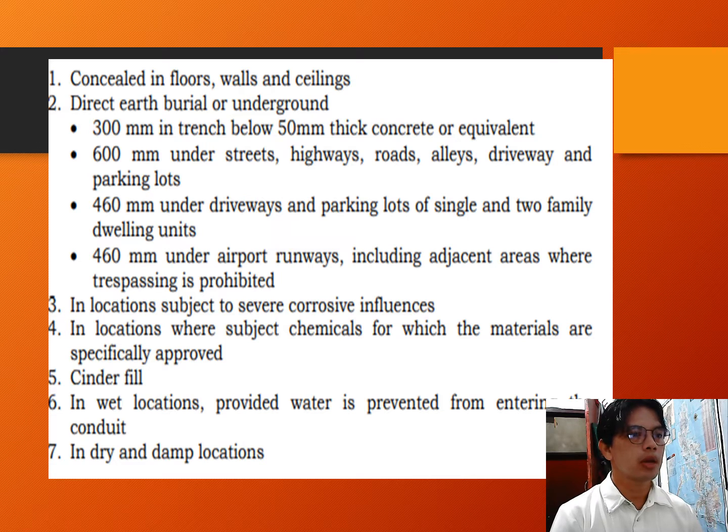Number two, direct earth, burial or underground. It is about 300 mm in trench below 50 mm thick concrete or equivalent. So it depends upon the size of the PVC. It's either 1/2, 3/4, or 1 inch, or even bigger PVC. It depends upon the wires to be installed inside that PVC.